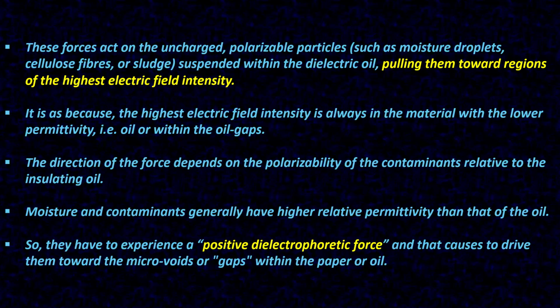These forces act on uncharged polarizable particles such as moisture droplets, cellulose fibers, or sludge suspended within the dielectric oil, pulling them toward regions of the highest electric field intensity. It is because the highest electric field intensity is always in the material with the lower permittivity, that is oil or within the oil gaps.